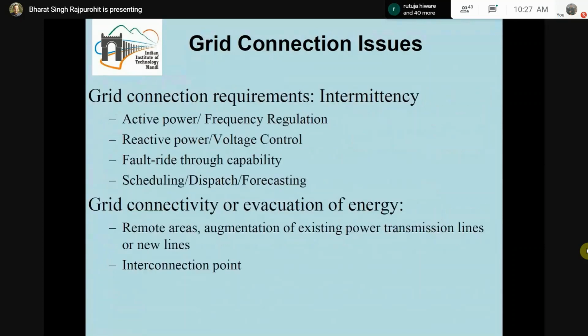What are the grid codes? Some of the grid codes are listed here, and we will discuss each grid code in detail. The broader grid codes are active power or frequency regulation, reactive power and voltage control, and fault ride-through capability, meaning that whenever faults occur in the system, a particular resource should be able to overcome such abnormal conditions, remain connected to the grid, and participate in the power exchange.